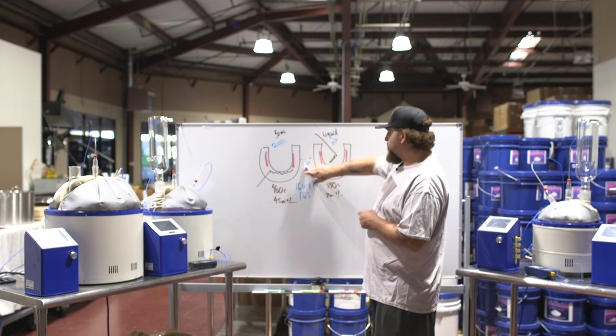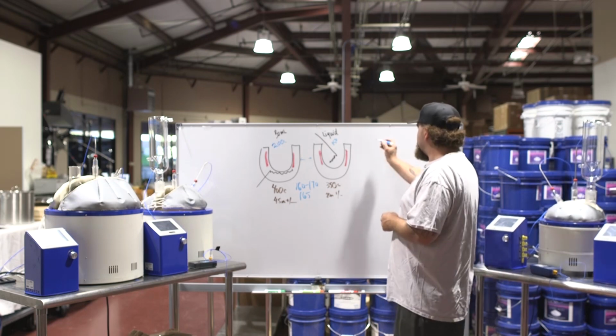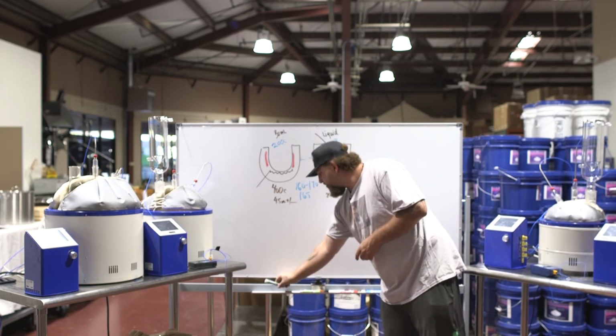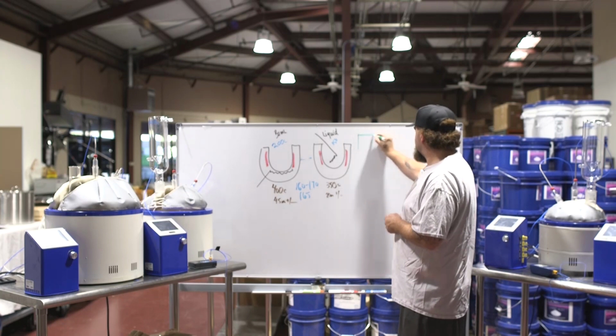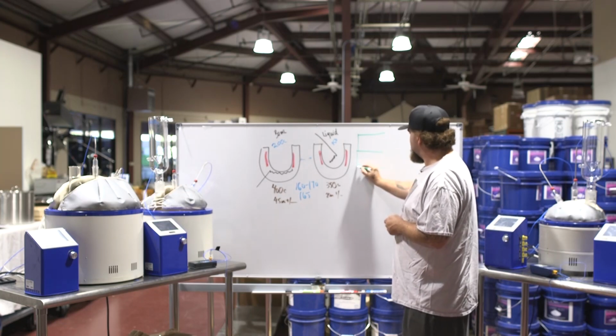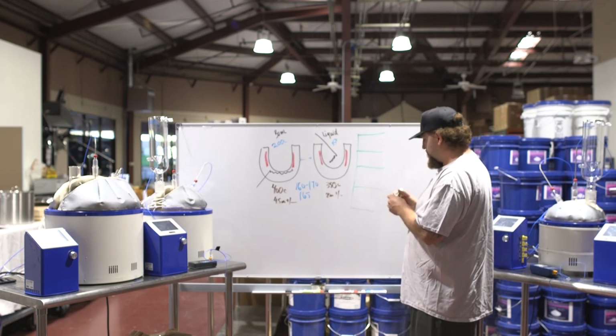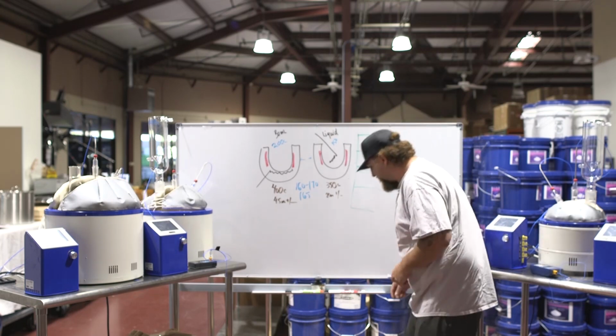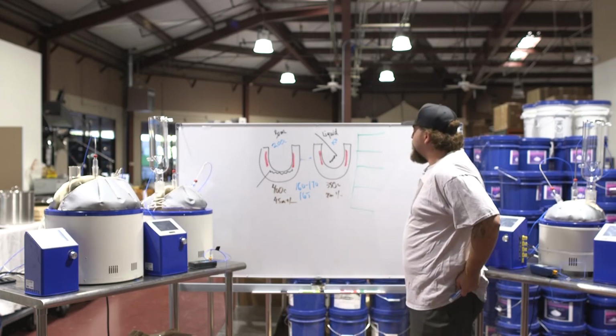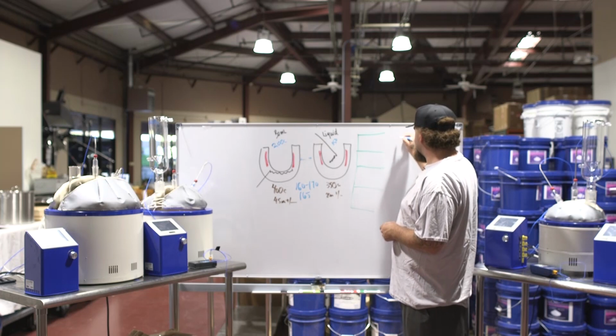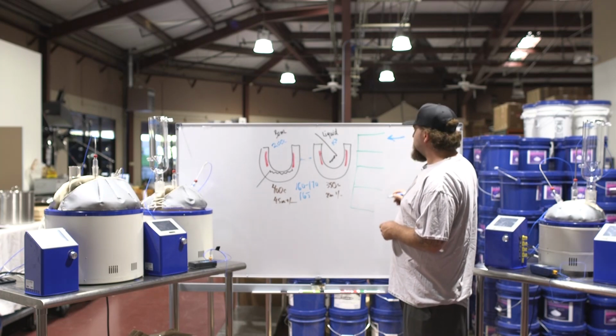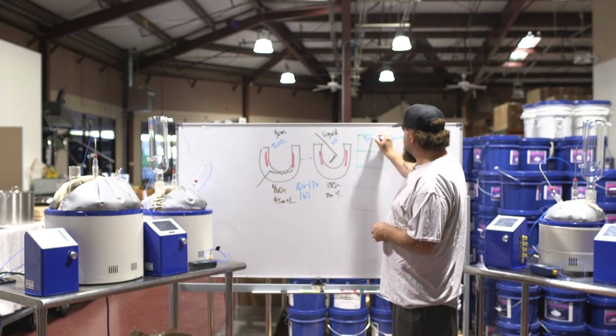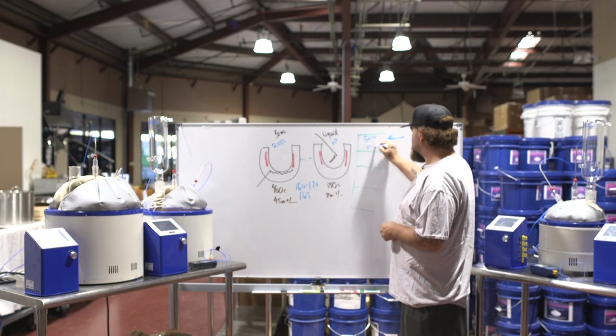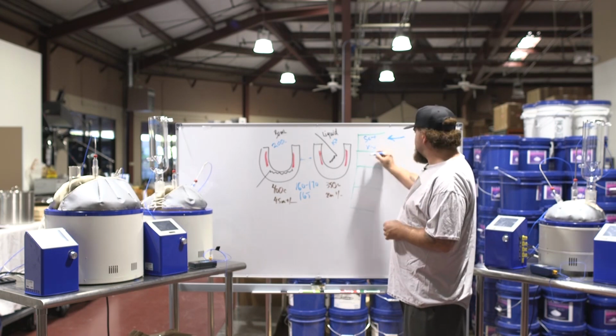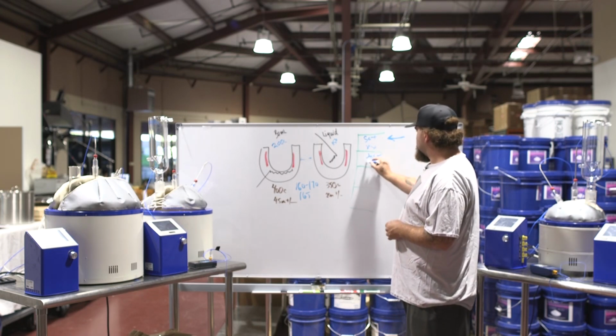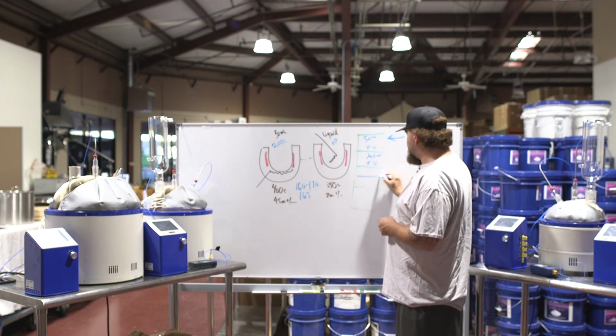Now, what's the difference when you run it? The difference is on the PID setting, your first PID is going to be, let's see if I can get this. So if you're running with the bowl, then your main temperature will always be right here. So this is where your set will be, and this is what it is. And the same thing, usually the jacket, that one doesn't change. Now we have the liquid side.